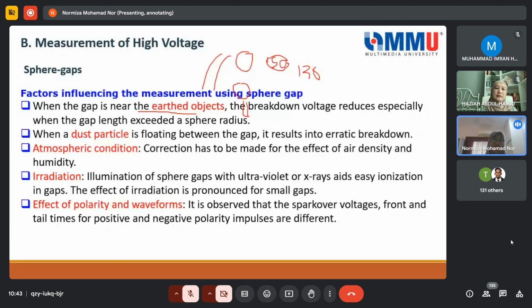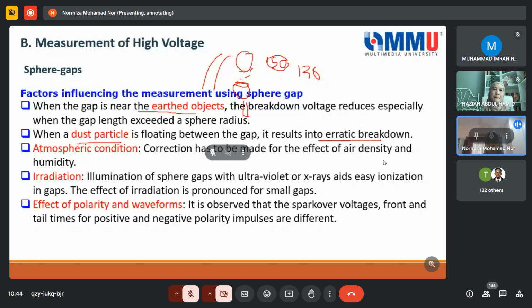And then next, when a dust particle is floating between the gap, so you may have dust around it, or even on the surface, moisture and so on, then it results in erratic breakdown. So it's a heavy loud bang or high flashover from this equipment or from this sphere gap.